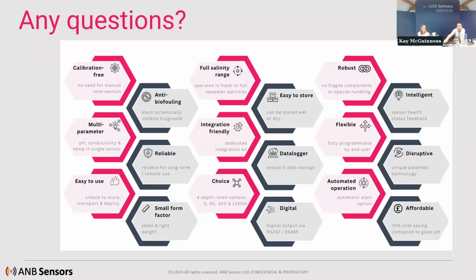Easy to store - these sensors are stored wet or dry on the shelf, easy enough, no worries. We log data internally on the sensor, so you have a backup system should your communication fail. In future releases, you'll be able to switch that off if you wish - it's up to you. Digital comms 232 485.